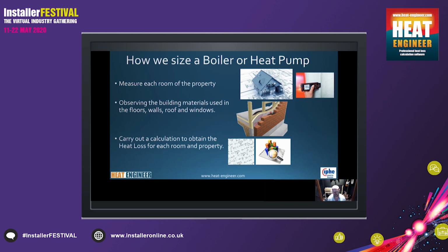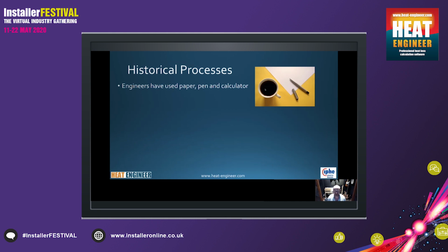If you get the pipework sizing and the heat loss sizing wrong with heat pumps, you are moving into very, very dangerous territory. We've all heard horrendous stories of companies going out, fitting heat pumps, in other words, removing gas boilers, etc., but putting in heat pumps using existing circuitry, and actually just causing their clients untold pain because their utility bills go through the roof because the heat pumps can't run in their sweet spot. So it's more and more important now to actually get those calculations correct, and especially your downstream pipe sizing to make sure that it runs at the correct delta T or temperature difference.